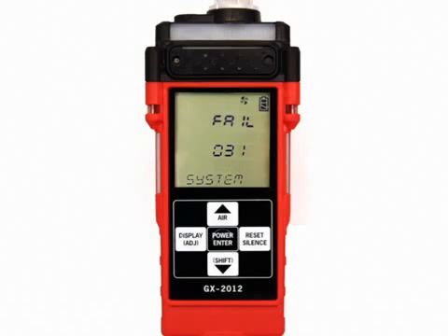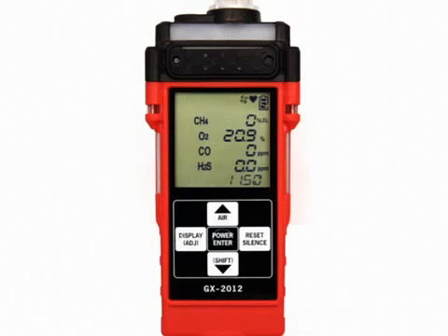If the error code is 031, you may press and release the Reset Silence button to continue to normal operation if the instrument must be used temporarily. There will be no data logging function if you operate the instrument after a 031 system failure. If your unit experiences a microprocessor failure, the heart symbol at the top of the screen will be steadily on or steadily off. The unit cannot be used in this case. Contact RKI Instruments as soon as possible.